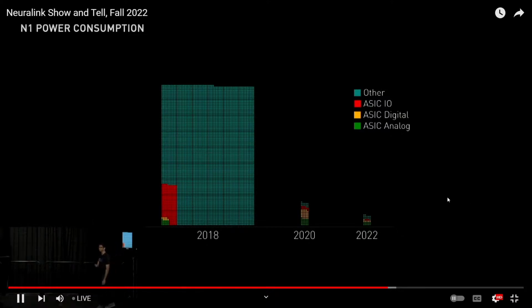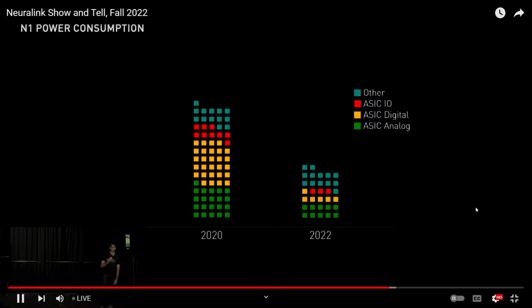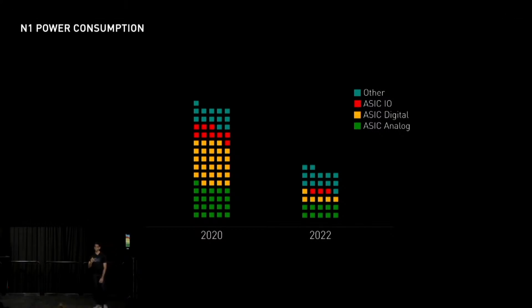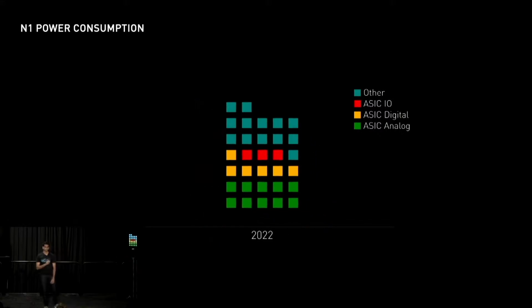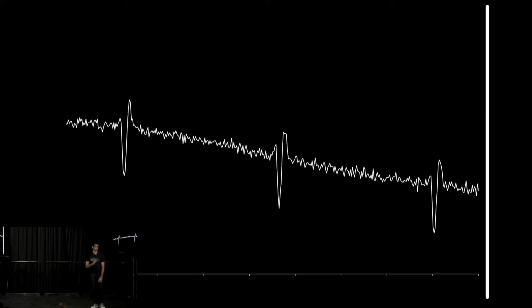Sending every sample from every channel off the device for processing. So simply monitoring for these spikes and only sending these spike events off the implant acts as a very efficient form of compression. And over the past 2 years, we've continued to make optimizations within the ASIC, dropping the total system power consumption down to just 32 milliwatts and doubling battery life. Let's take a look at our on-chip spike detection algorithm, which makes our battery-powered implants possible.